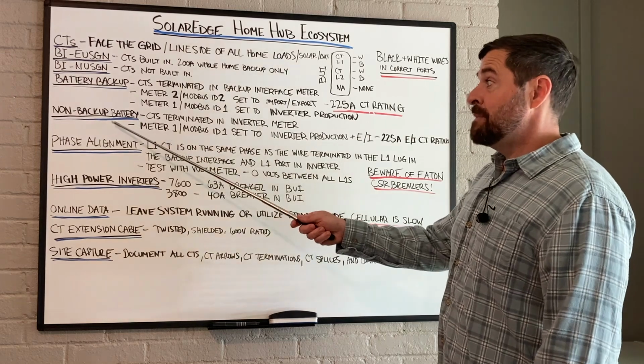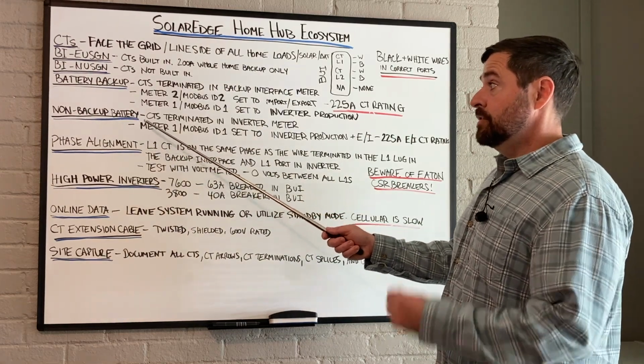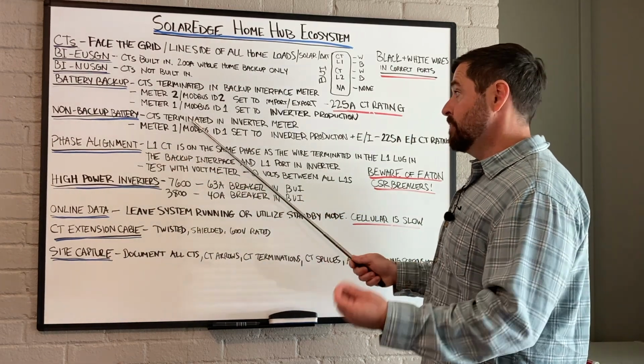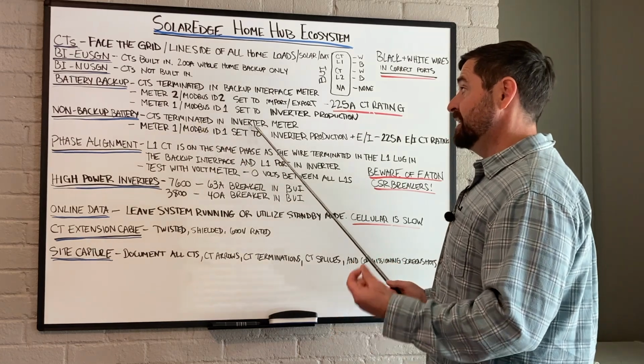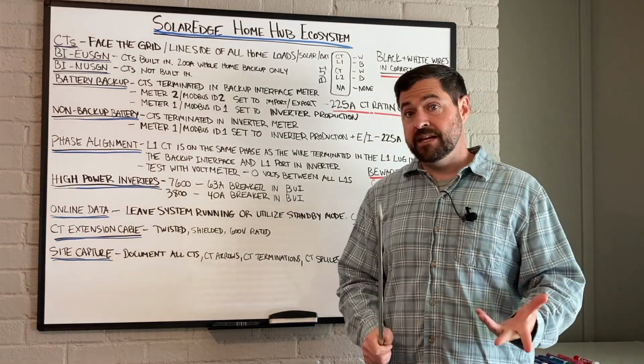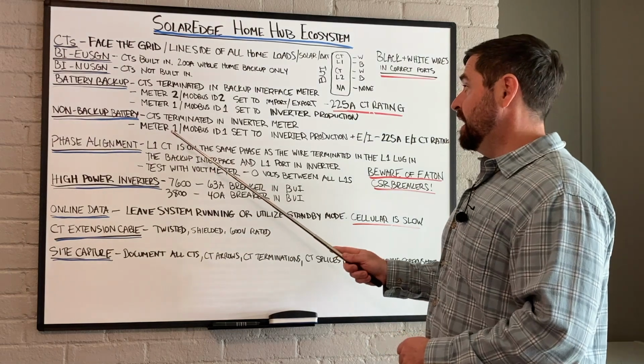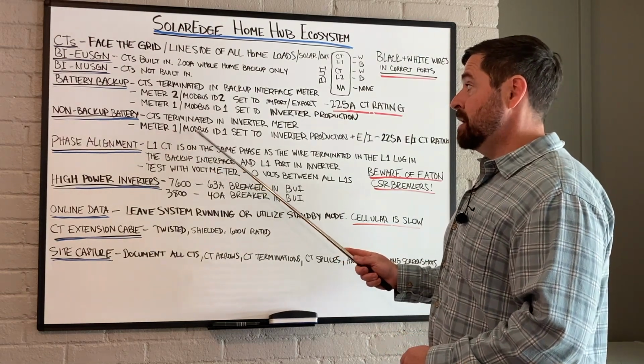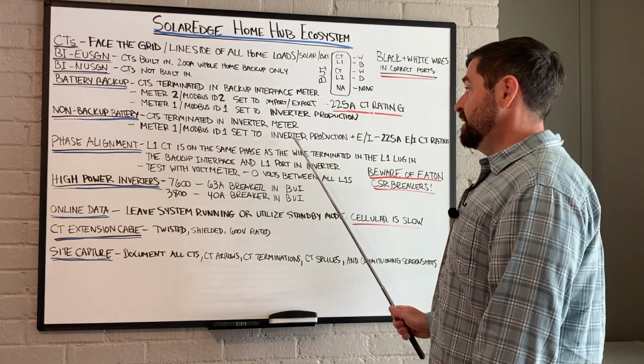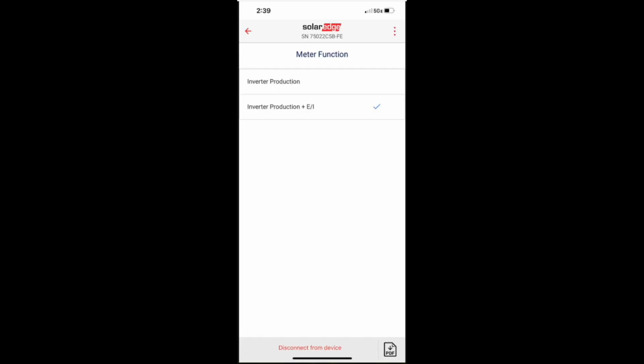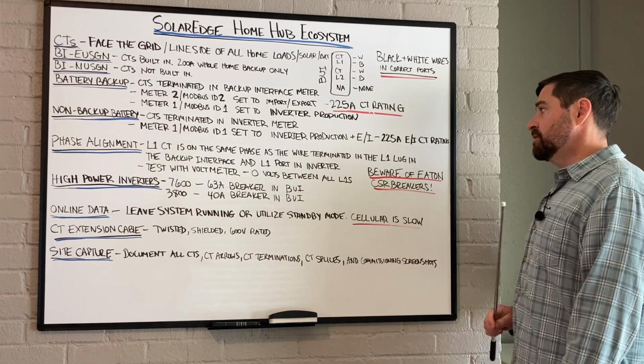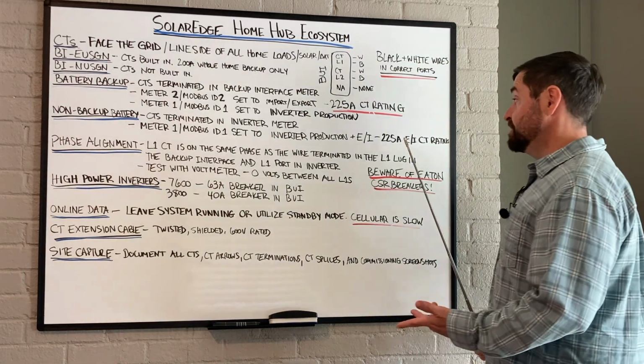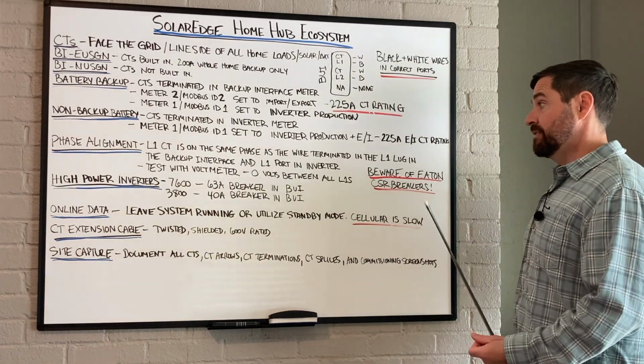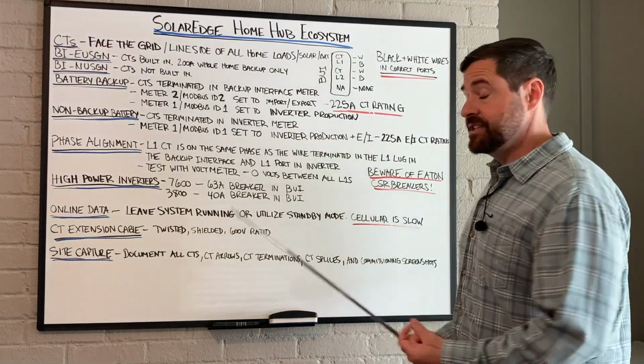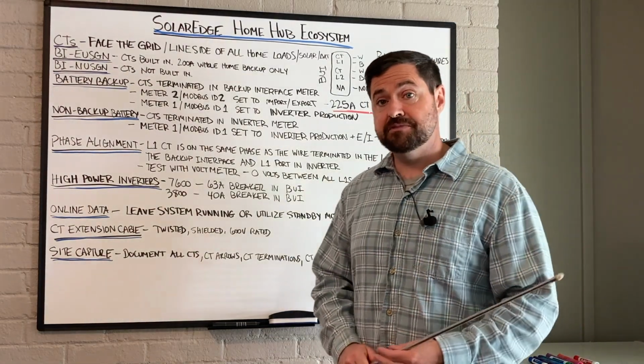So for these non-backup battery systems, you have no backup interface. So all the CTs are going to get terminated into that energy meter inside the inverter. And you're going to set meter 1, or Modbus ID 1, to inverter production plus E/I. And again, make sure you set those CT ratings for the consumption CTs to 225 amps. I believe the built-in production CT is a 50 amp CT.